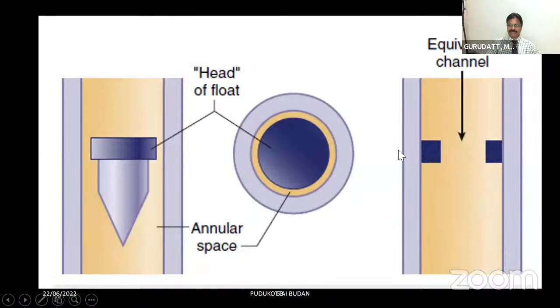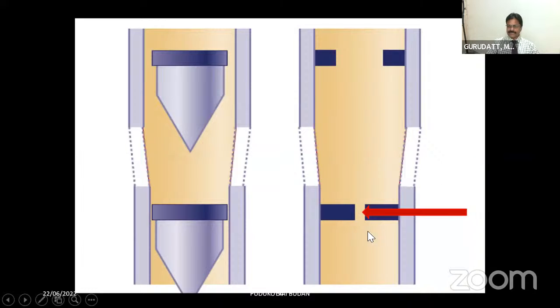So I was talking to you about the annular space. This annular space is between the upper margin of the bobbin and the inner margin of the flow meters. Here I am depicting it as an equivalent channel. This equivalent channel is much smaller at lower flows and larger at higher flows. At lower flows, you can see the height of the space is much longer compared to the width. That's why the flow here is laminar flow, or tubular flow, because it's a tube here. And as you go up the flow meter for higher flows, the length is much smaller compared to the width of the annular space.